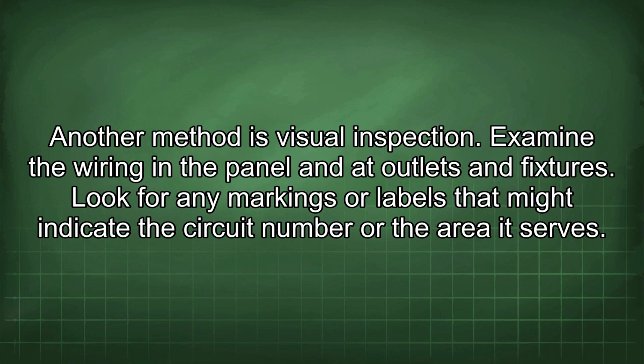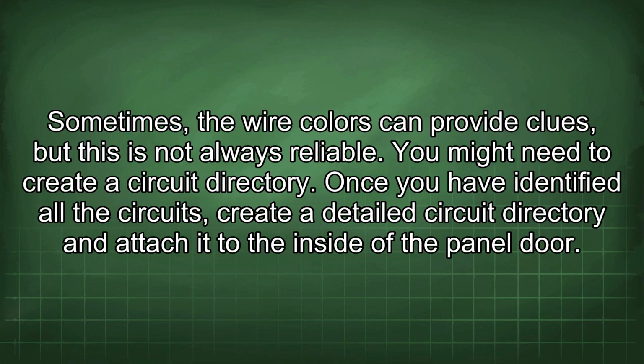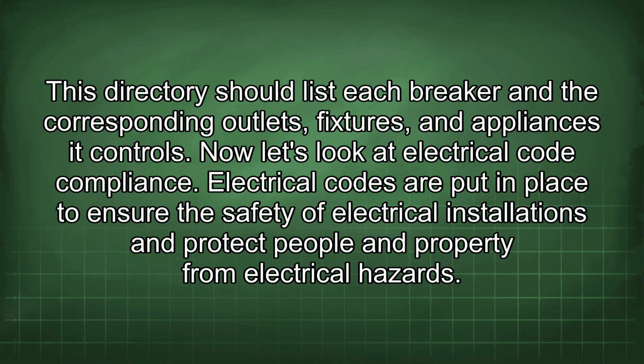Another method is visual inspection. Examine the wiring in the panel and the outlets and fixtures. Look for any markings or labels that might indicate the circuit number or the area it serves. Sometimes the wire colors can provide clues, but this is not always reliable. You might need to create a circuit directory. Once you have identified all the circuits, create a detailed circuit directory and attach it to the inside of the panel door. This directory should list each breaker and the corresponding outlets, fixtures, and appliances it controls.